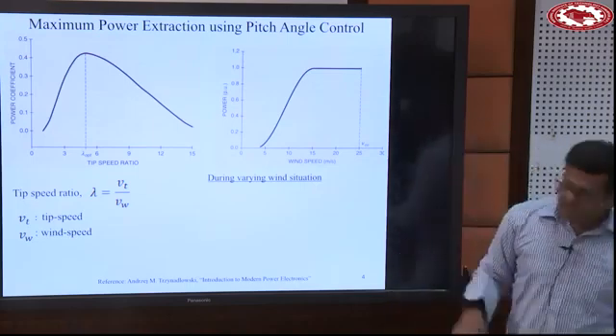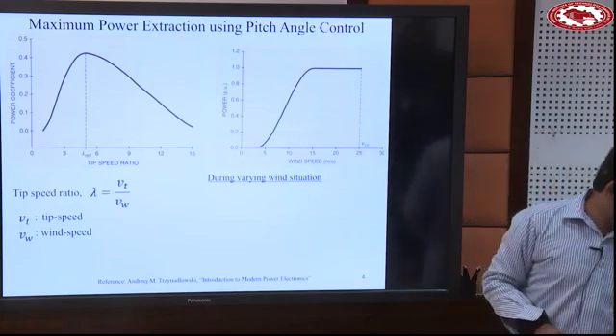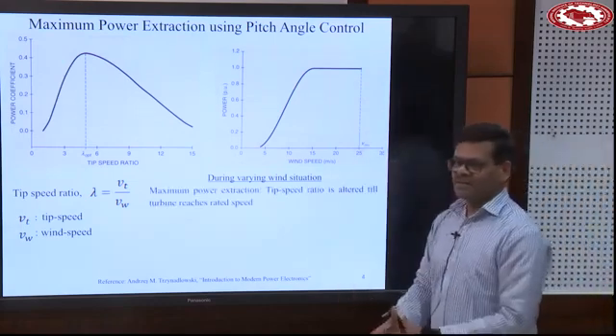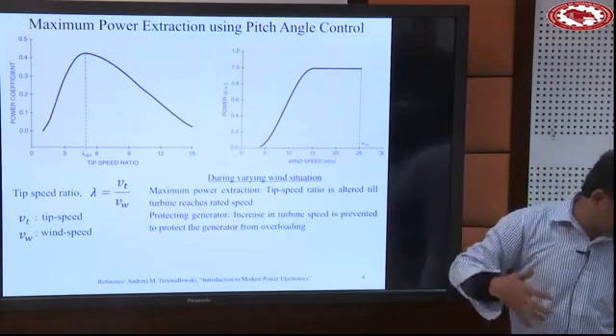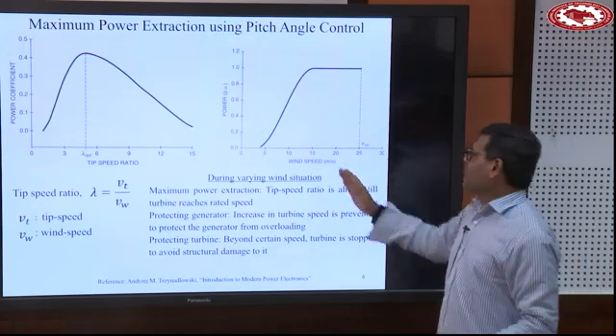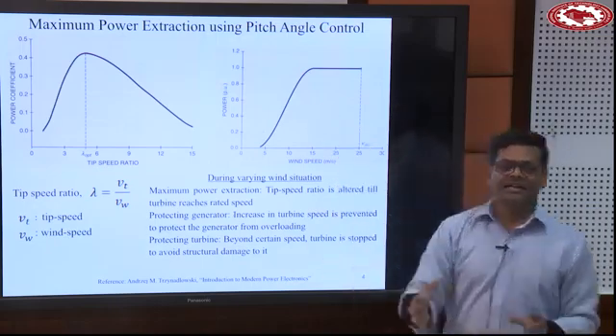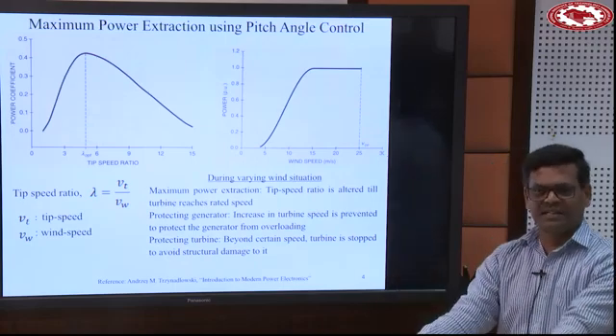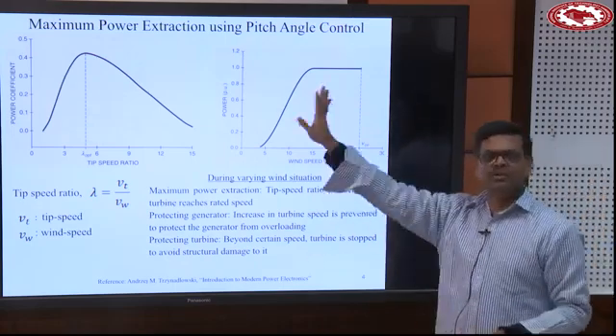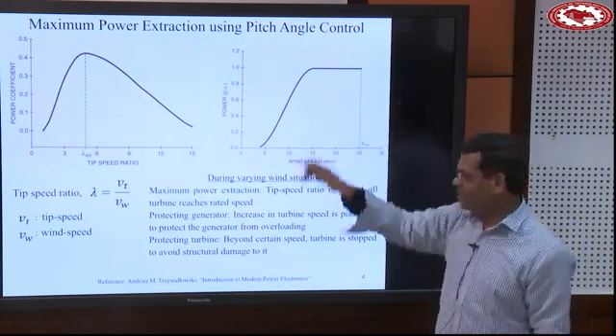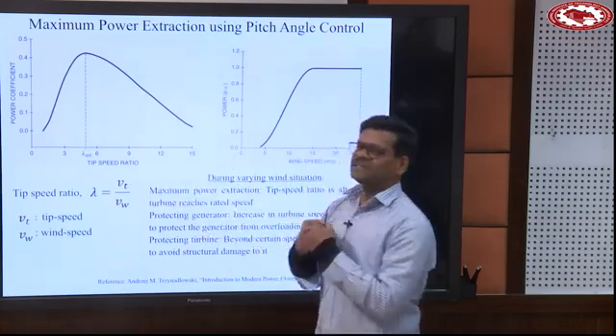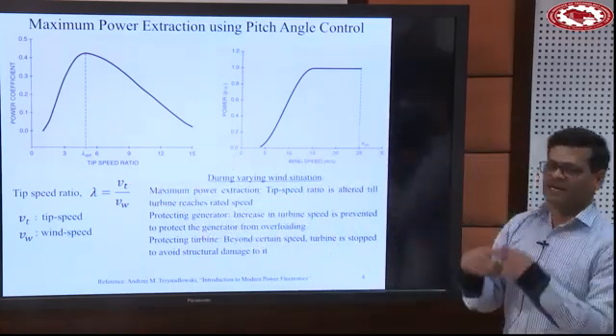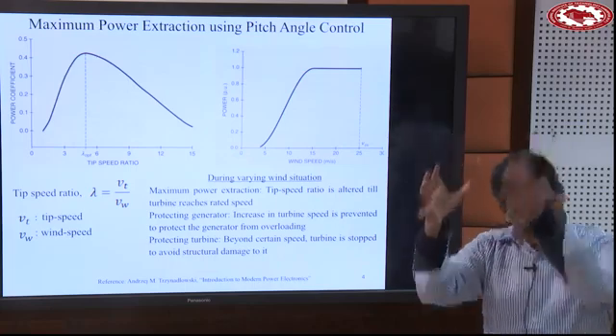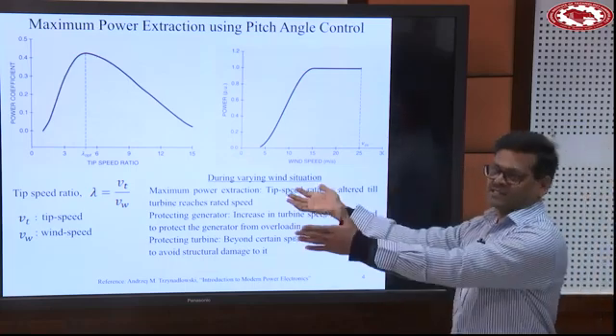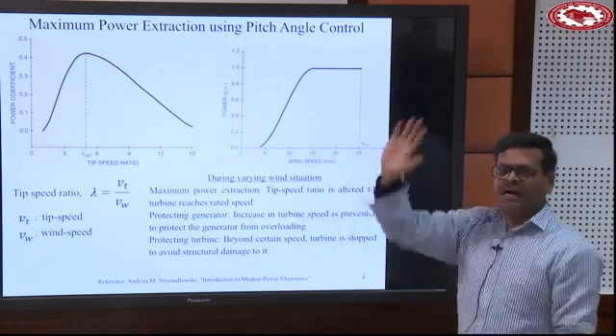All right. But after 25 meter per second, the turbine that is made is unable to withstand the mechanical power that is coming out. From 15 to 25, it is to take care of the electrical integrity of the system. The generator we have already installed cannot give more than that. So therefore, we are doing pitch angle control of the turbine blade such that the energy converted from wind to mechanical to electrical is optimized at that level. But after 25 meter per second, it is huge. Whatever turbine we have installed cannot withstand that speed. Turbine in the sense, I am not talking about the tower, I am talking about the blade.